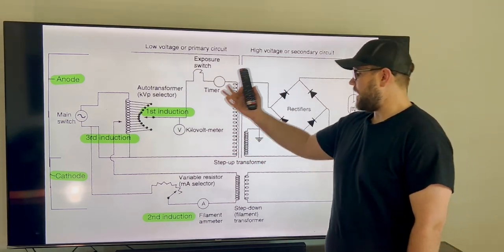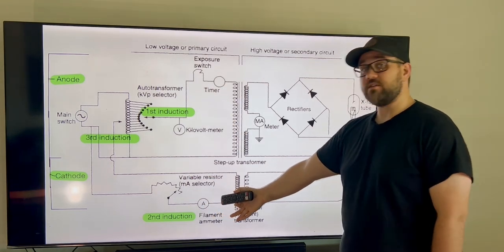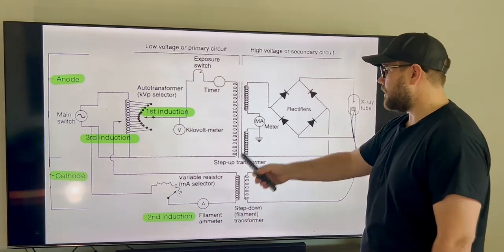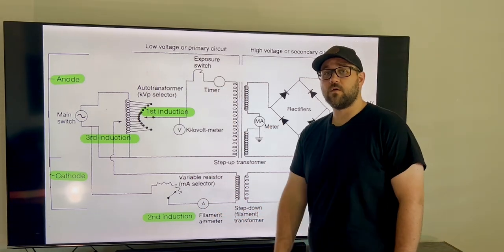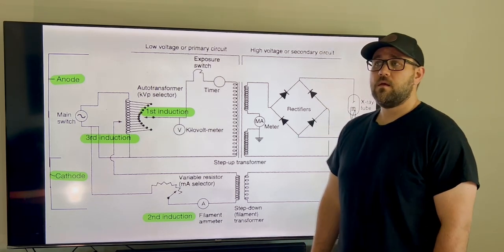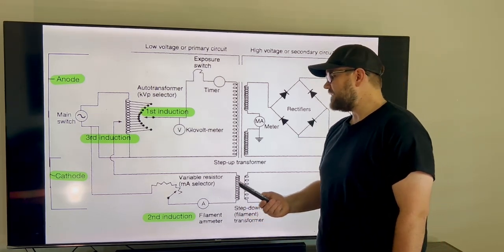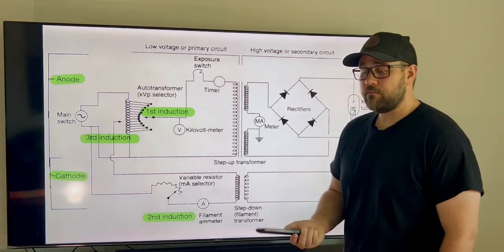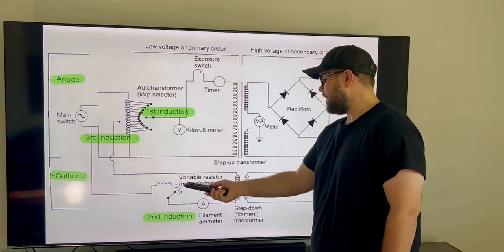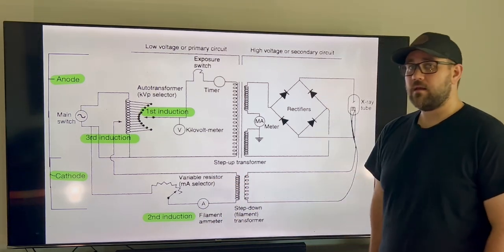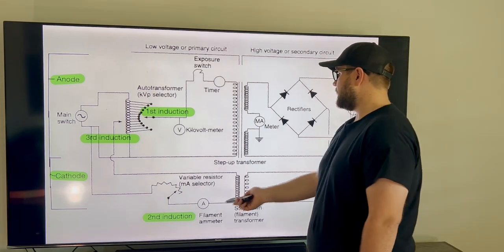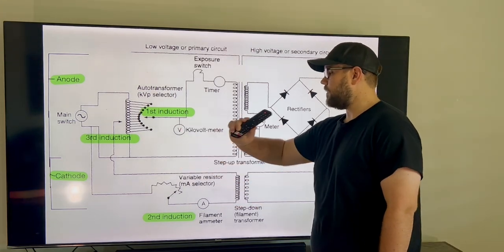In the same aspect, we're going to be down here at our second induction, and this is going to be our variable resistor or our mA selector. It's going to read our 80 mA, it's going to set itself, and it's going to be read by the filament ammeter, and it's going to continue on around up through here.